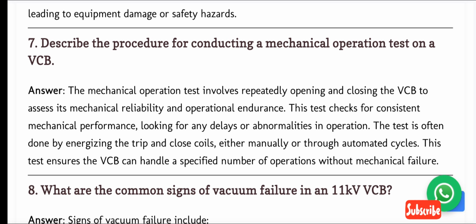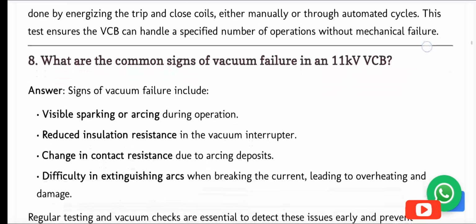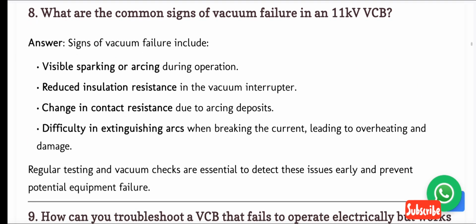Answer. The mechanical operation test involves repeatedly opening and closing the VCB to assess its mechanical reliability and operational endurance. This test checks for consistent mechanical performance, looking for any delays or abnormalities in operation. The test is often done by energizing the trip and close coils, either manually or through automated cycles. This test ensures the VCB can handle a specified number of operations without mechanical failure. 8. What are the common signs of vacuum failure in an 11 kV VCB?